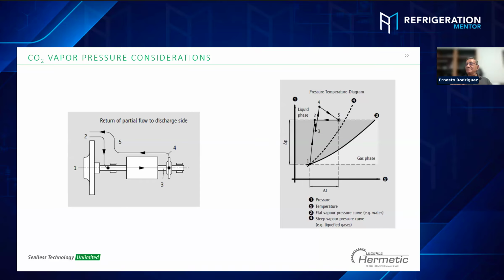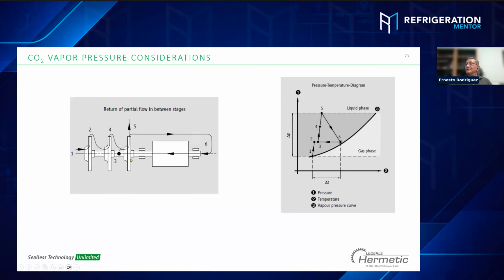Okay, how is the pump moving, how is the vapor created inside the pump? Basically, I showed the diagram of how the fluid moves inside the pump, but we have gas, and we want to prevent this gas flashing inside the pump. We can see number 4 is the highest pressure in the system, in one impeller, because this is the way we increase the pressure to move the refrigerant. When we run the pump, we want to prevent this gas phase in the CO2 pump. The same applies to the multi-stage.